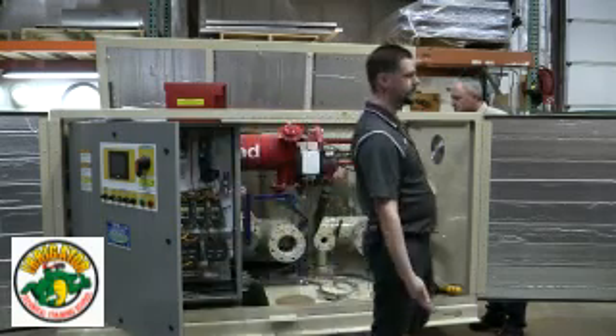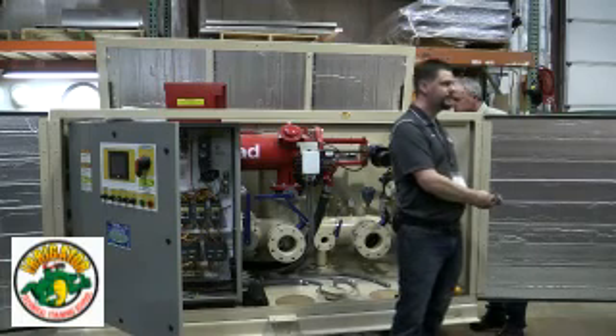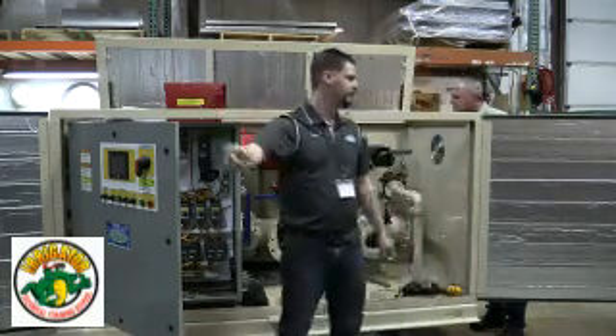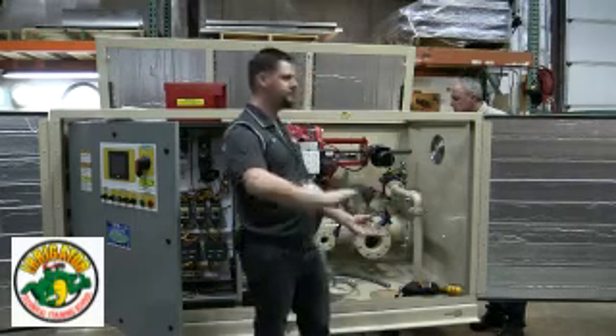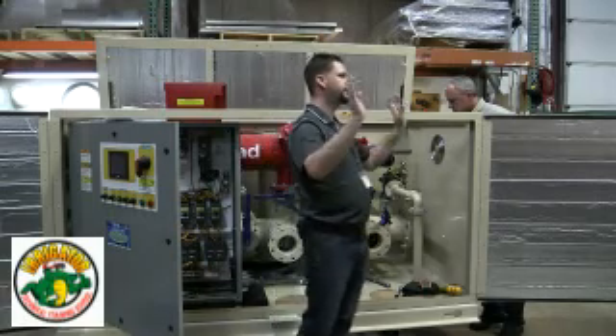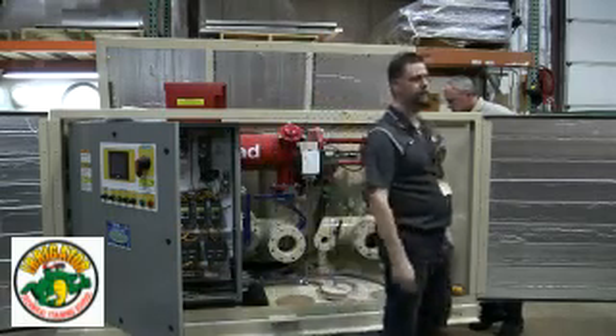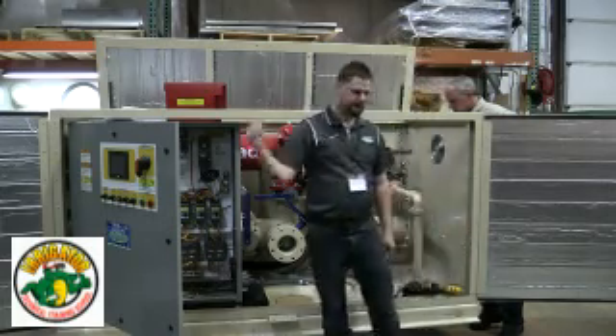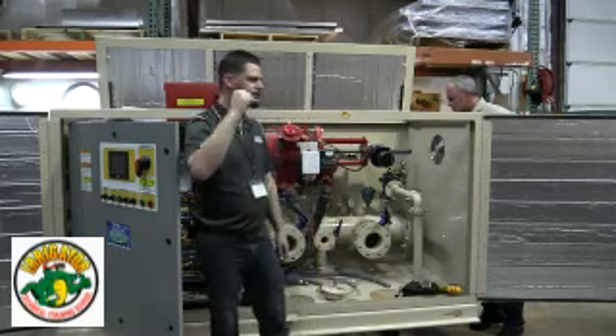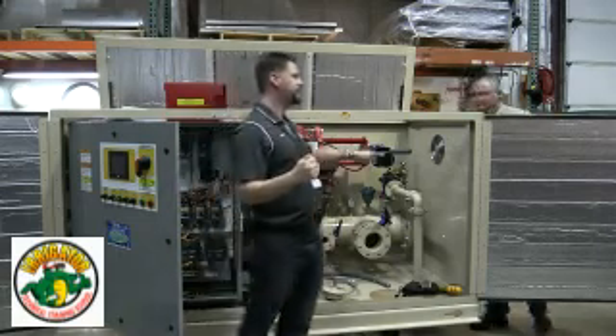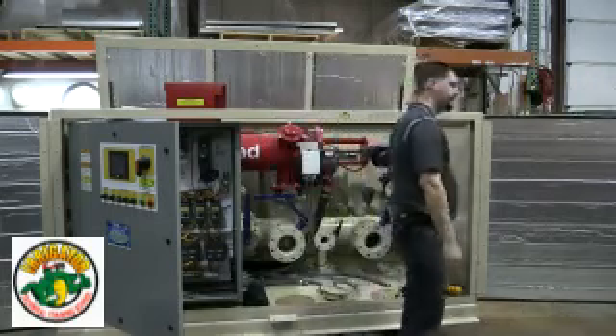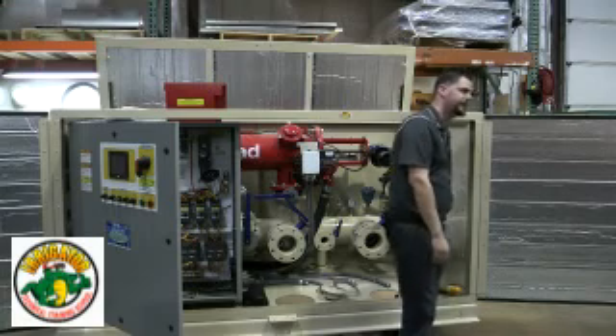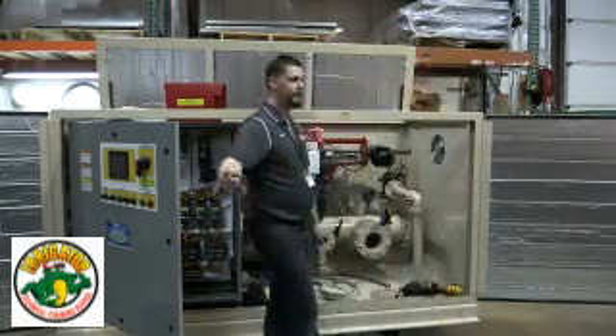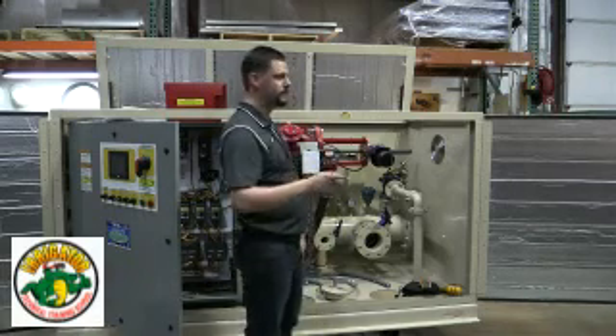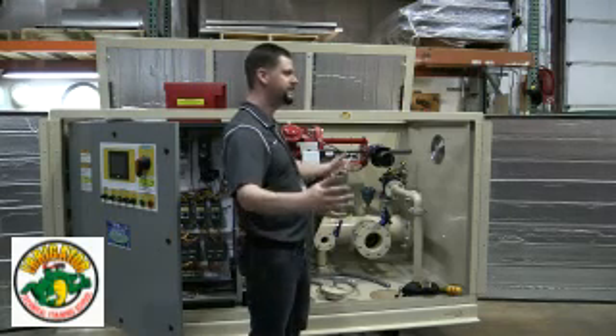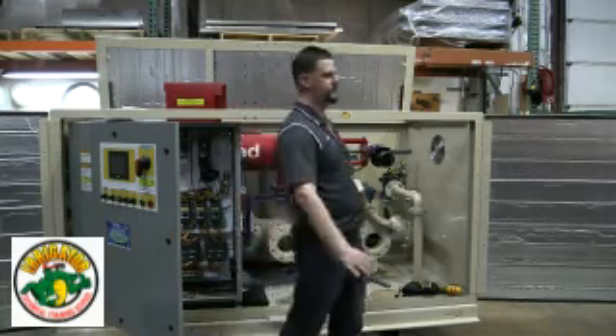Because it serves really a couple of purposes. If a pump doesn't slow down fast enough when a valve closes, whatever, deceleration time, extra pressure is created, that can just go out and nobody even cares. Also, if you have a very big zone that's way down the road and it's running full bore, all these pumps are going, and that valve just goes shunk. This sends back a shock wave all the way back to the pump station. And if you don't have the pressure relief valve adjusted properly, that pressure has nowhere to go. So you get a bounce back of the shock wave. Boom, boom, boom, boom. Then you end up with 20 pounds above your set point static, which nobody wants.